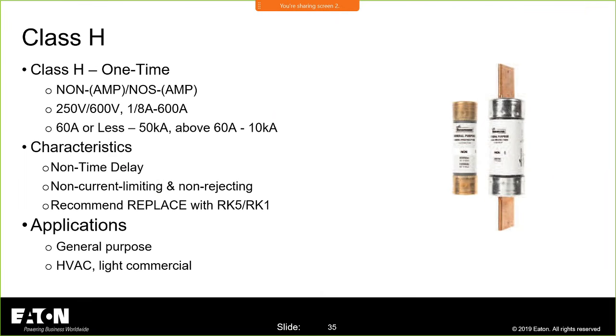Your class H, I'm not going to give this one a name. We'll just call it H. Okay, just H. Not H for anything, just H. You have the NONs, which are your 250 volts, NOS, which are 600 volts, up to 600 amps, non-time delay, non-current limiting, and I would not recommend these. You know where you'll find these? HVAC equipment. You know why? Because they're the lowest cost solution.